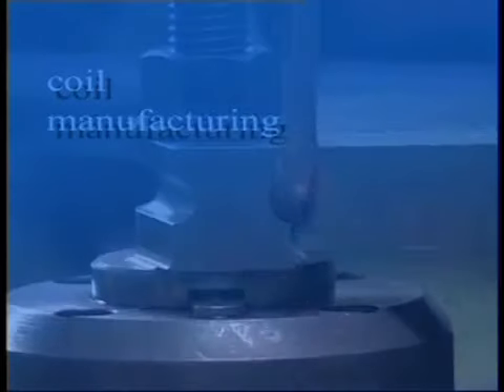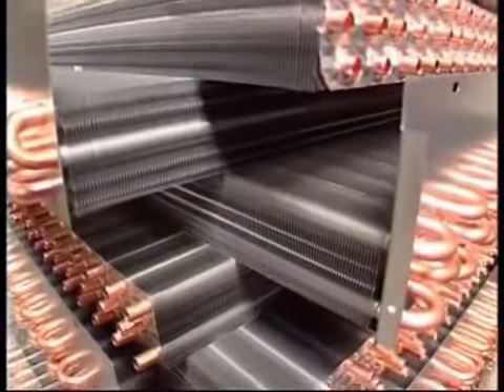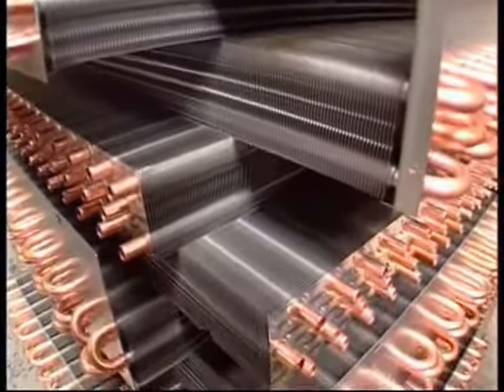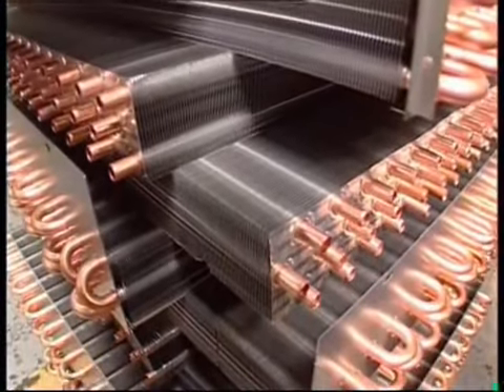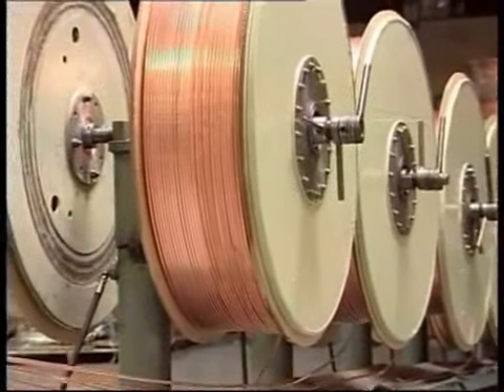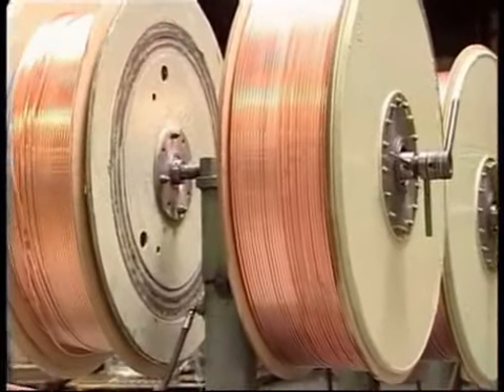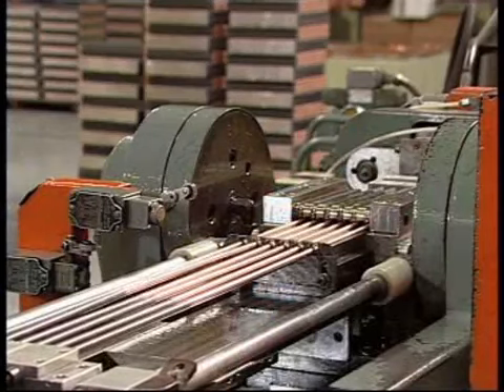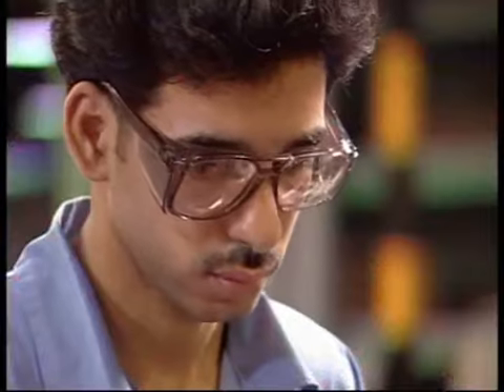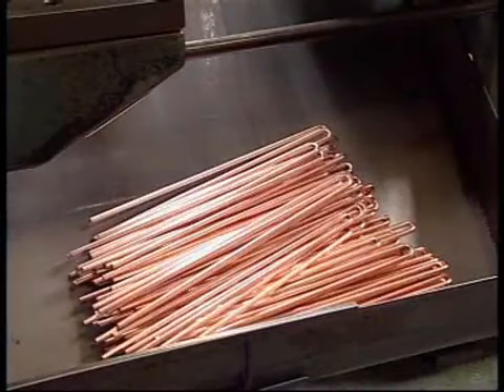One essential component in air conditioners must be the heat exchanger in its dual application as a condenser as well as evaporator. Changing from smooth-bore copper tubes to internally enhanced inner groove tubes enabled a move towards higher efficiency heat exchangers. The process of coil making includes the use of hairpin tube cutting and bending machines, which draws the tubes from the copper reels, cuts them to the required length, and bends them 180 degrees.